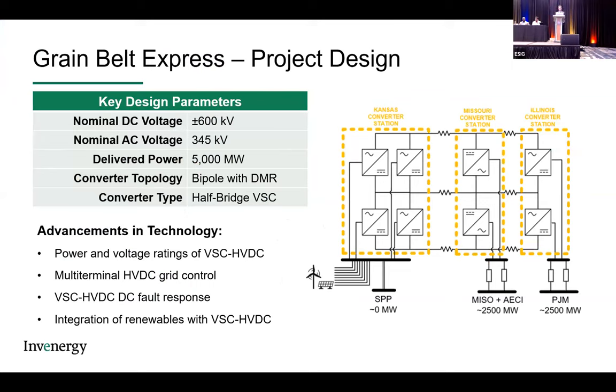So looking at the Grain Belt Express, we can dive a little into how the HVDC line looks. I said earlier, the DC voltage is plus or minus 600 kV bipole. And you can see the two converters that Eugen was talking about on either side here. Each bipole is approximately 2,500 megawatts. So you end up with two converter stations working in parallel to send the power: on the SPP side, one 2,500 megawatt converter in the Missouri part, and then another 2,500 megawatt converter in the Illinois part. All the AC side connections are 345 kV.